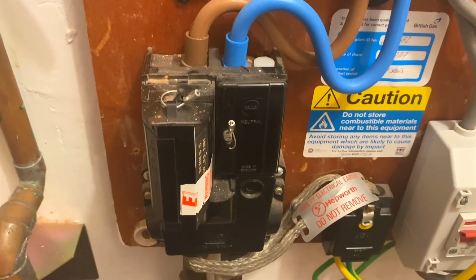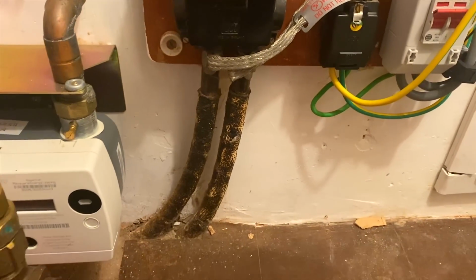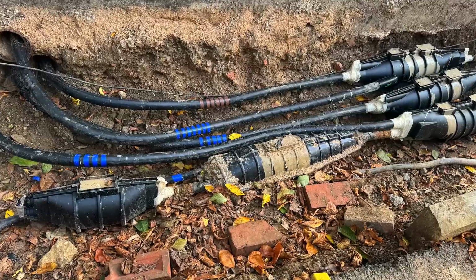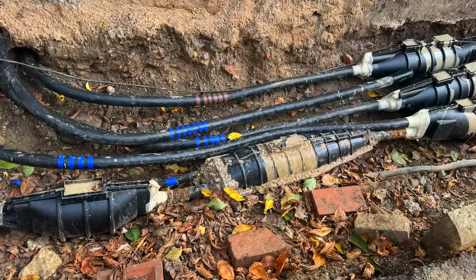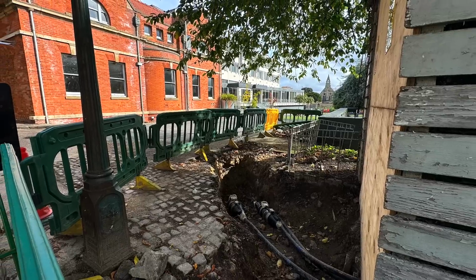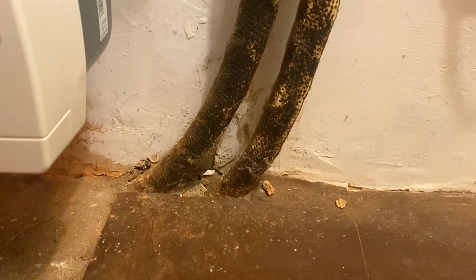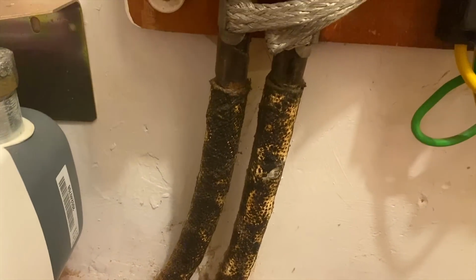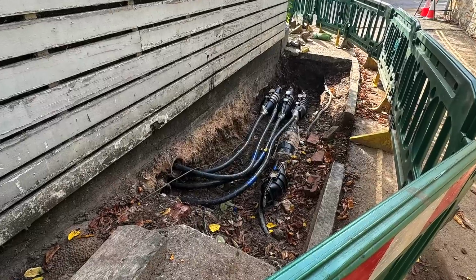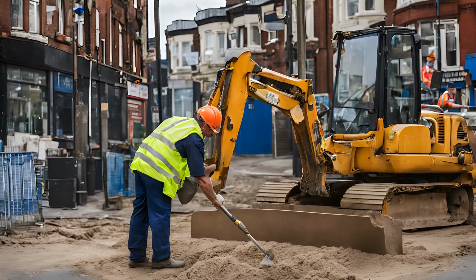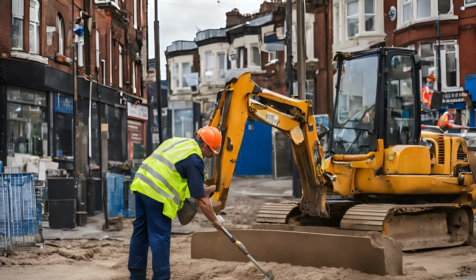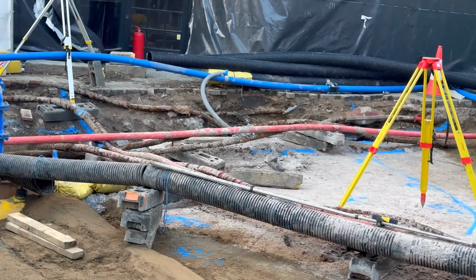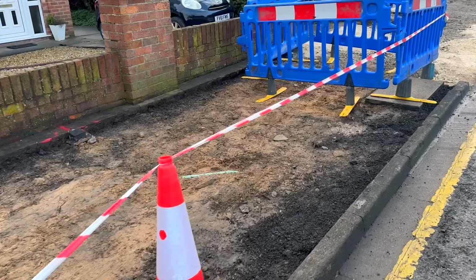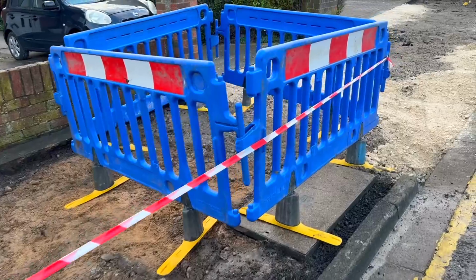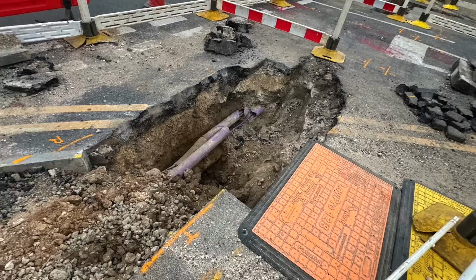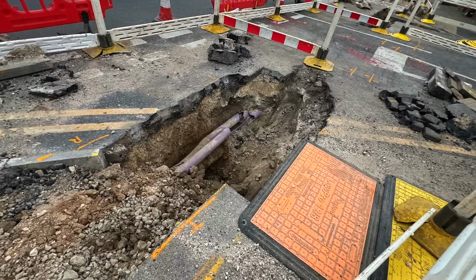So why are incoming supplies changed to a TNCS PME system? A DNO may upgrade a TNS system to a protective multiple earthing system as part of electricity supply repairs. This typically occurs when service cables and joints on paper insulated lead covered cables, or PILC, fail underground. To address these issues, DNOs often connect the supply neutral to an earth electrode using combined neutral and earth cables. Over time, this process can result in some DNO networks transitioning to a TNCS and PME system. It can happen underground. In fact, it would be very difficult to determine exactly what the earthing arrangement is due to the amount of work which the DNO has conducted on its network.